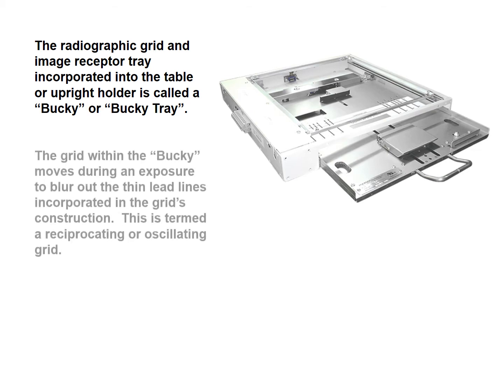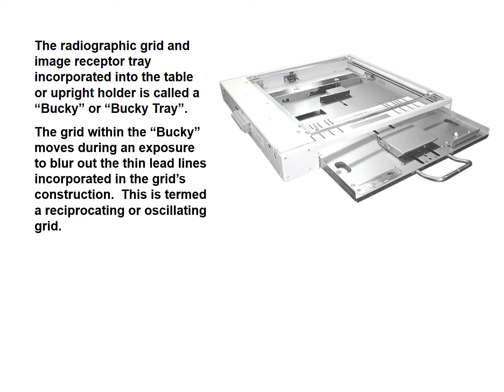The radiographic grid and the image receptor tray are incorporated into the table or the upright holder, and of course that's called the bucky or the bucky tray. The grid within the bucky moves during the exposure, and why it moves is to blur out the thin little lead lines that are incorporated into the grid's construction. And remember, your grid within your bucky can either be reciprocating, having a back and forth type of motion, or an oscillating grid, which is more in a somewhat circular motion.